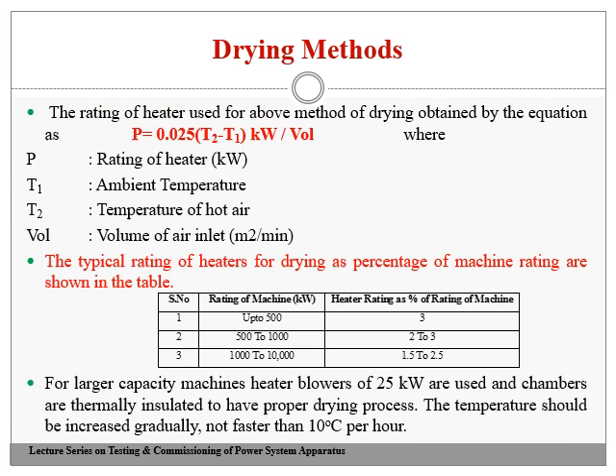Now we'll see what the rating, the capacity of that heater should be in terms of kilowatts. The rating of the heater used for the above method of drying is obtained by an equation, which gives the kilowatt capacity of the heater that I should use. I cannot use a 10 kilowatt resistor for drying out a 1 HP motor. It depends upon the motor size and capacity.